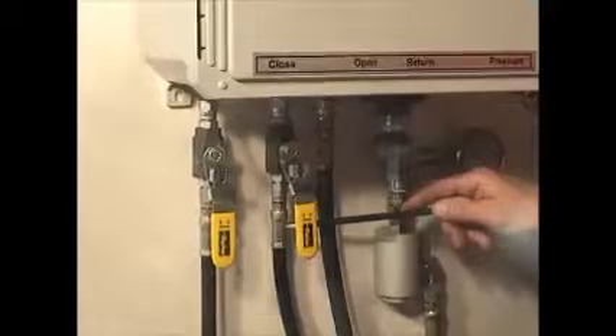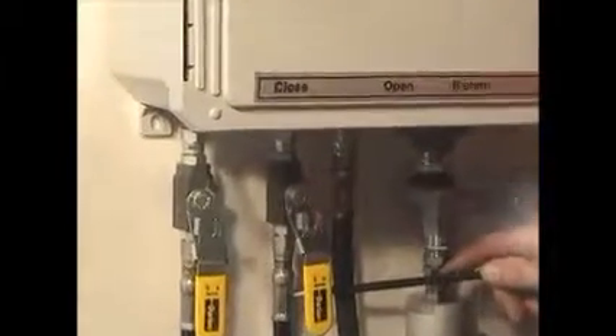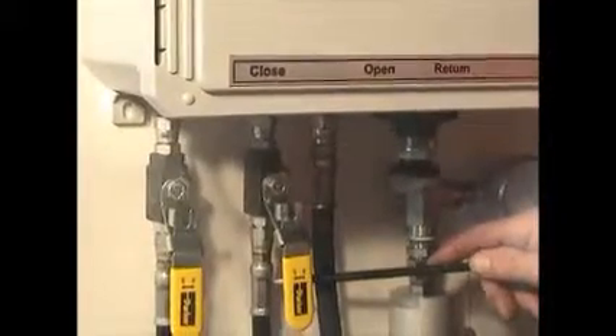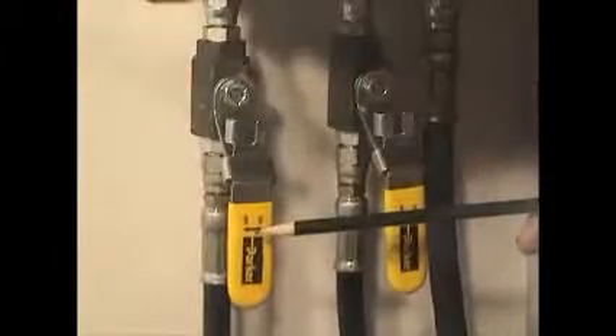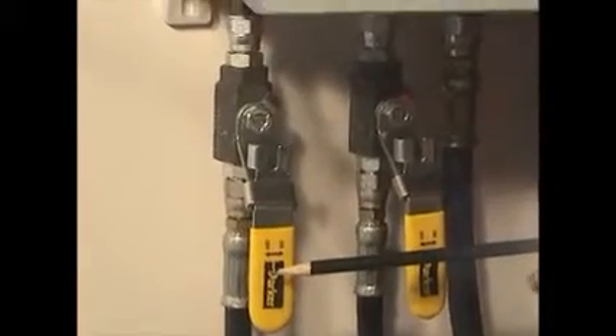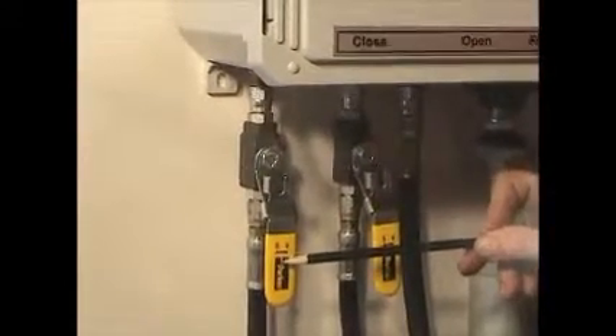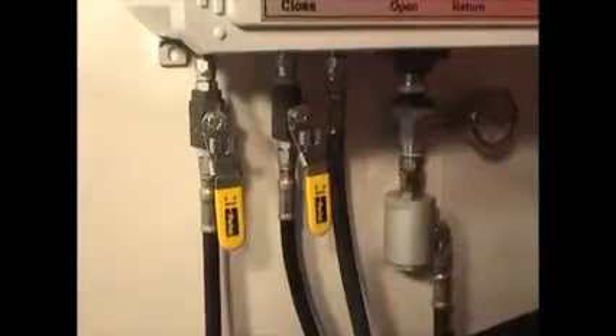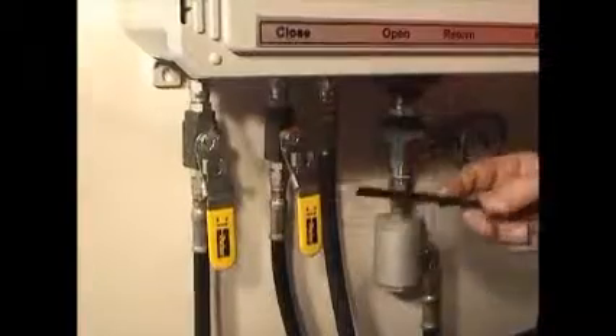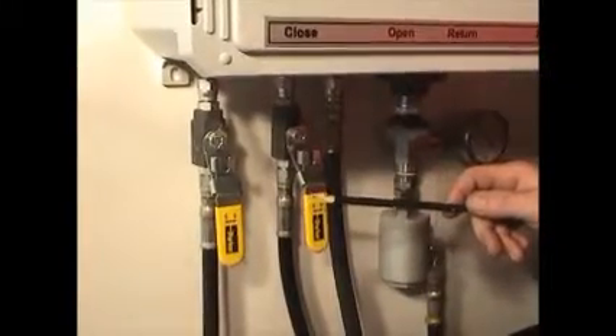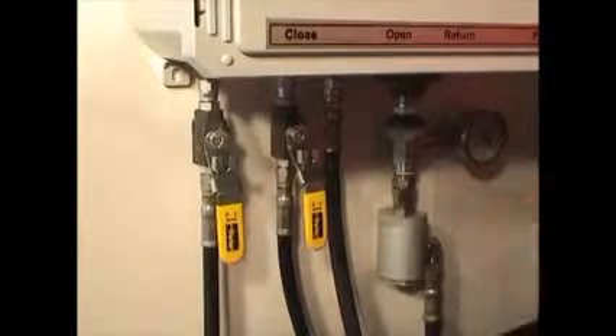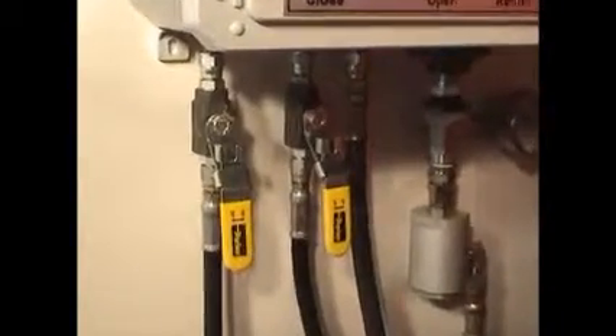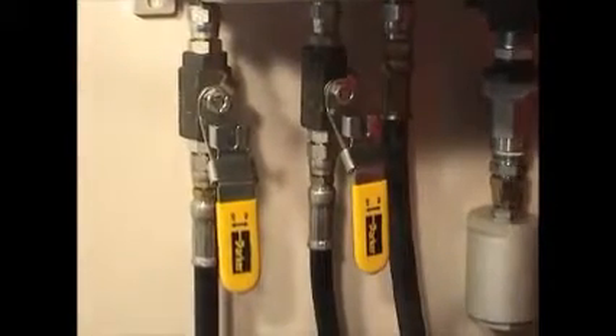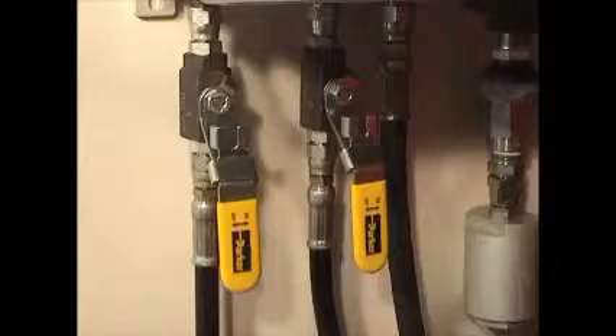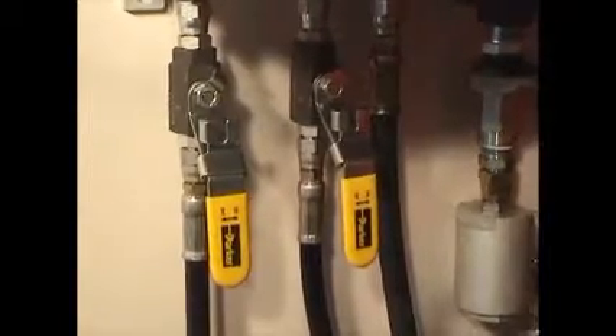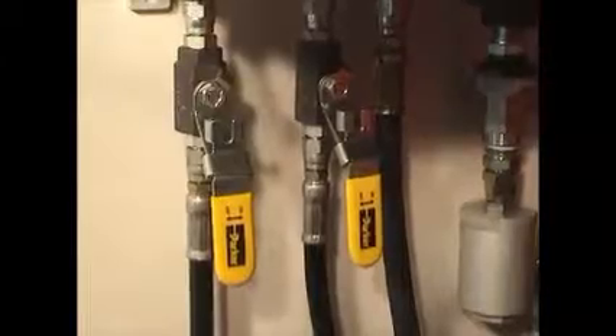The second hose from the left attaches to the open side of the hydraulic cylinder on the butterfly valve located under the water. The left-hand hose attaches to the closed side of the hydraulic cylinder, controlling the butterfly valve located under the water. Both the hydraulic open and closed hoses have lockout valves attached to them. These valves must be locked out anytime repair or maintenance is being performed to the hydraulic cylinder or to the butterfly valve. This is to prevent any accidental opening or closing of the butterfly valve in the event a person's hands are near the hydraulic cylinder or the butterfly valve.